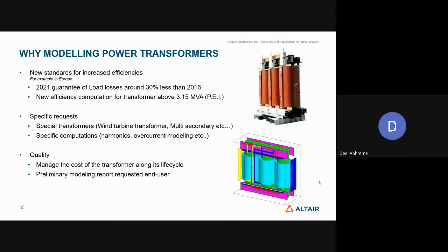And then we have new methods of computation of efficiency. We no longer follow the conventional efficiency computation. We had something very commonly which we learn as all-day efficiency, and different quantities of efficiency that we consider. We no longer consider those. All-day efficiency is now a rather outdated concept in developed countries, at least, where they have a new method called the PEI method. If you are interested, you'll have to read about it. It's a fairly complex method of computation, but it is more realistic in nature.